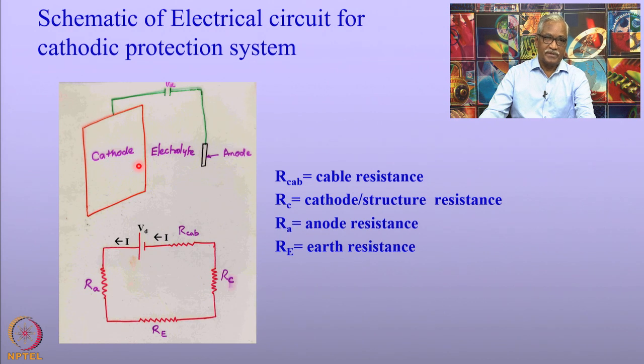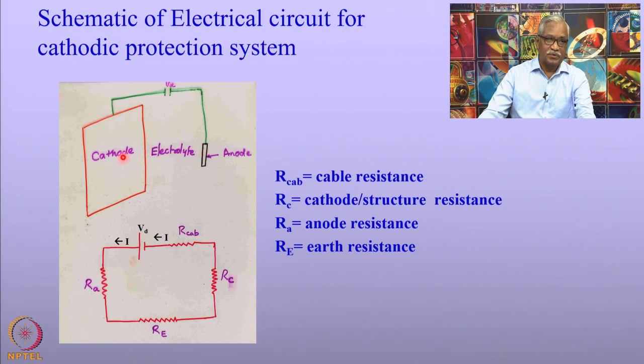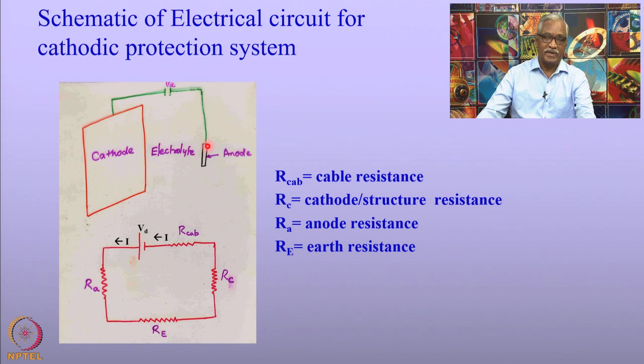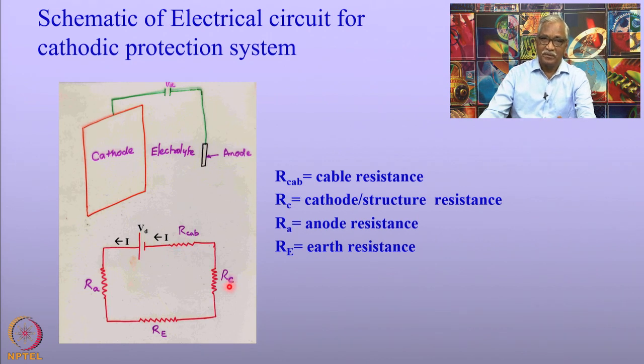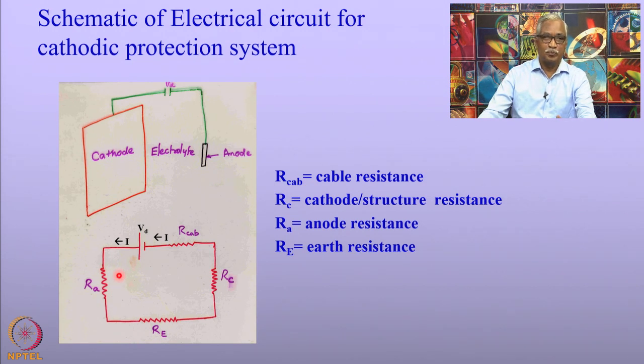Coming back to cathodic protection of structures, you notice that the current source — the anode — dissipates current in the soil, and then the current travels to the cathode and goes back to the rectifier. This current flow can be represented by a simple equivalent circuit consisting of several resistors: the resistance offered by the cable, the cathode, the electrolyte, and the anode. All these resistances are in series, offering resistance for the flow of current in cathodic protection of engineering structures.